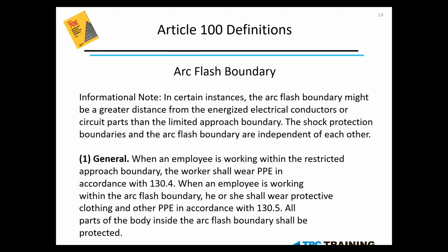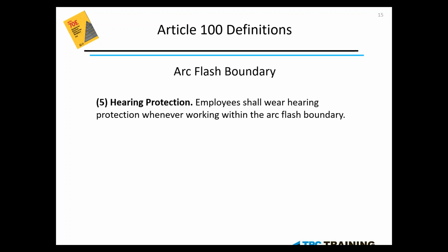We have our arc flash boundary, which is our heat boundary, and then here shortly we will talk about the shock protection boundaries, which are known as the limited approach and restricted approach shock boundaries. So our 3 boundaries are made up of the heat boundary and our 2 shock boundaries. Now, while inside that arc flash boundary, I think it's important to point out a couple of thought processes through our code book.